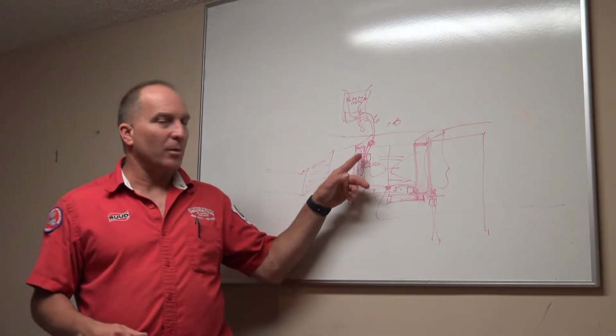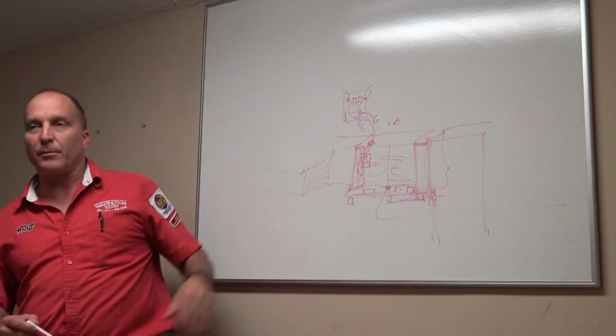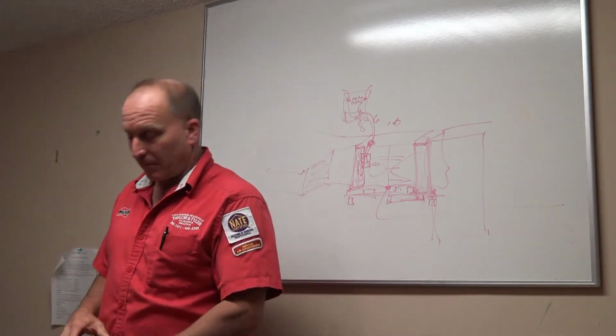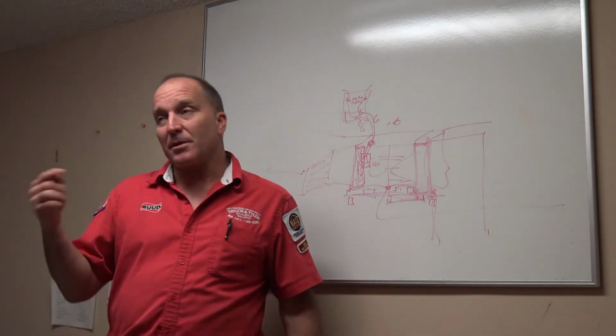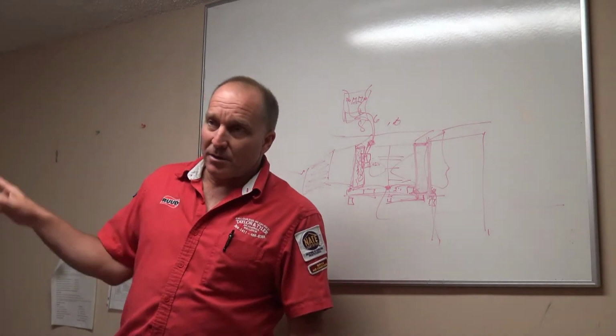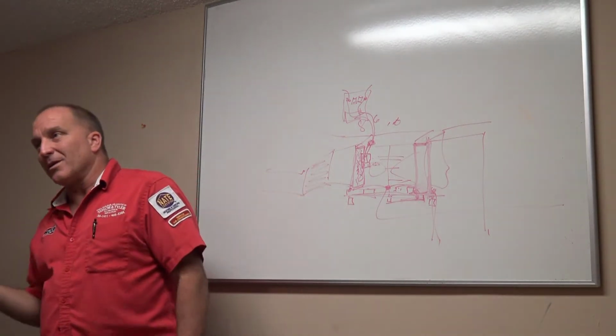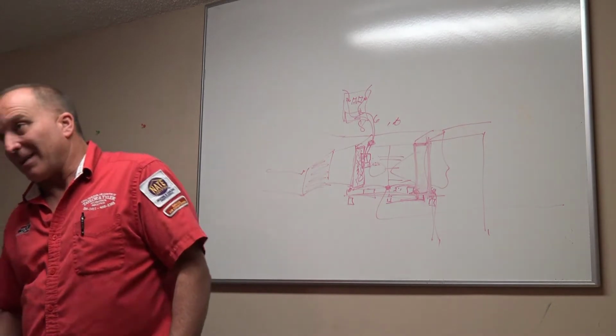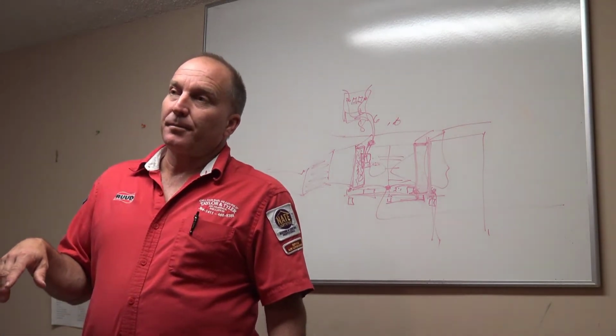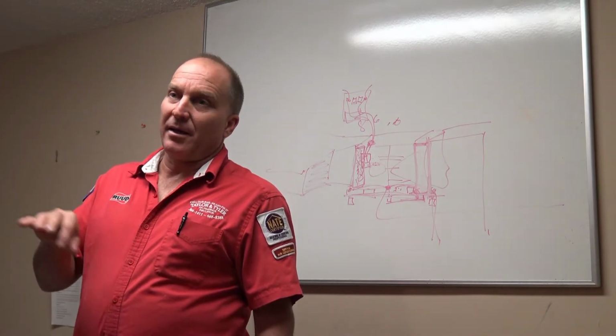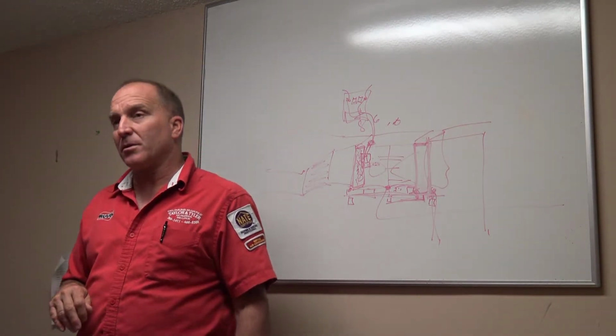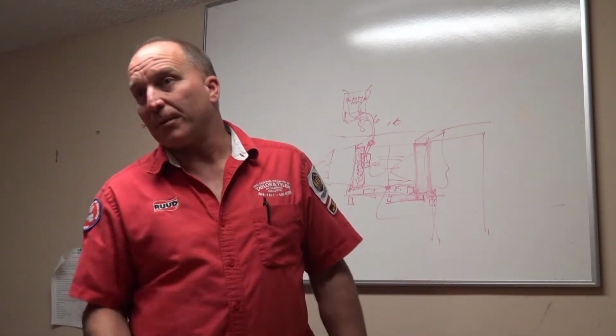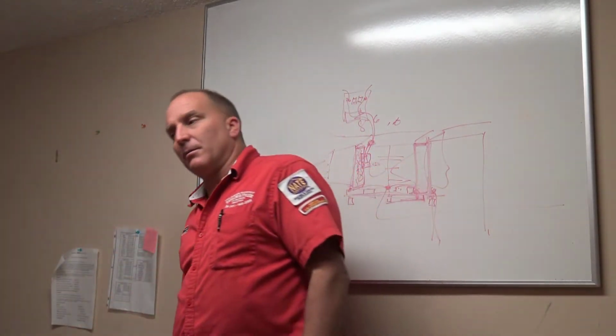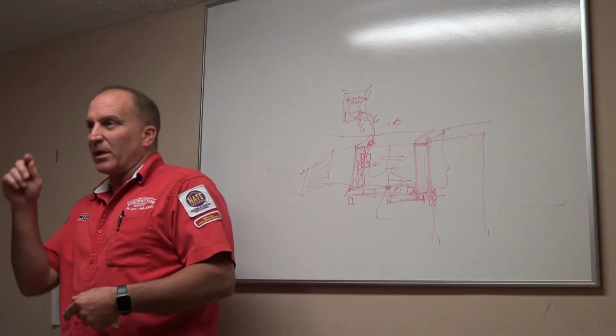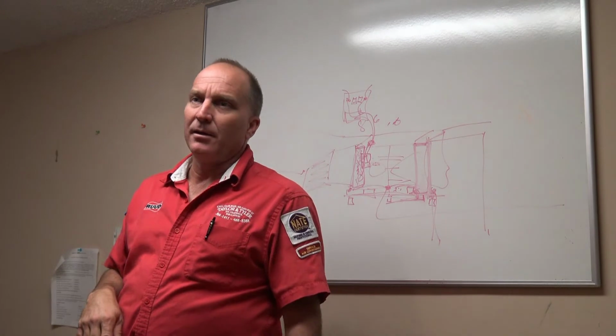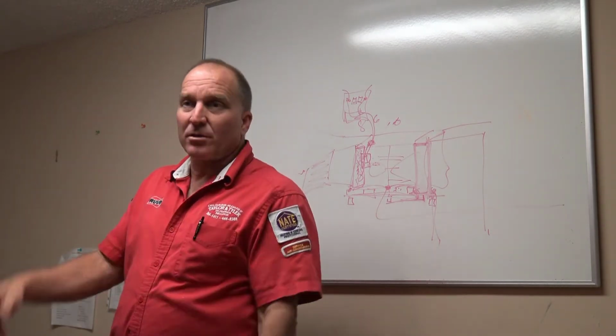Okay? So you always want to check that. And we have extra rubber pieces that we can put over there, but we don't give them away. We sell them, unless we install the system, because they should have them on our systems. If it's somebody else's, put it over it. If it's an old one, you sell it, you put it on, and you put a new breaker in. Because that's how you're going to stop that new breaker from condensating and having everything chewed up. You can also put some electrical liquid tape on it, or some grease, not oil, on your electrical connections up inside there in order to help it not sweat and cause rust, okay?